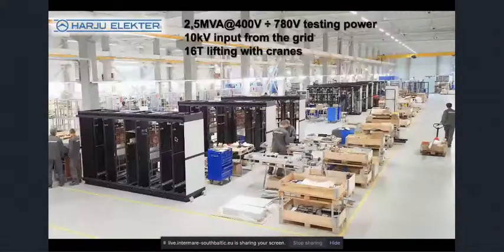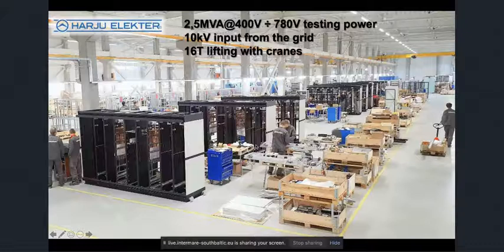Our core testing capacity on the low voltage side is from 400 to 780 volts, in steps of 20 volts, and we can test 2.5 MVA, especially liquid cooled systems. We design the liquid cooling, all the manifolds, pipings, connections, and heat extraction from the electronics and drives. Throughout the factory we have 16-ton crane capacity to lift transport units, systems, and containers with all the equipment.